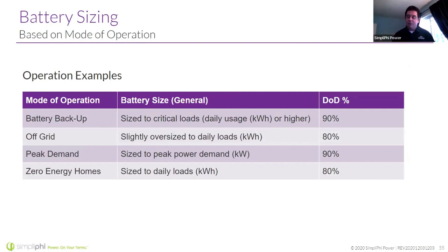Couple different examples of where we'd recommend different depth of discharge. Like we were talking about earlier with expansions, if you're letting your battery sit there, you can cycle it pretty deep. So for battery backup, maybe a couple dozen instances of usage a year, 90% depth of discharge is great. But if you're off grid and you're cycling that battery every day, or if you're doing time of use arbitrage, cycling that battery every day, 80% depth of discharge is appropriate. Now, maybe for the peak demand example, where it's really only covering the peaks of your demand for a couple of minutes, maybe 90% is appropriate, depending on the load profile for that user and how far you anticipate them discharging that bank. But again, for a zero energy home that's living off their batteries, off grid or grid tied, if you're using those batteries every day, 80% depth of discharge is appropriate because you will get that anticipated 10,000 cycles out of it.